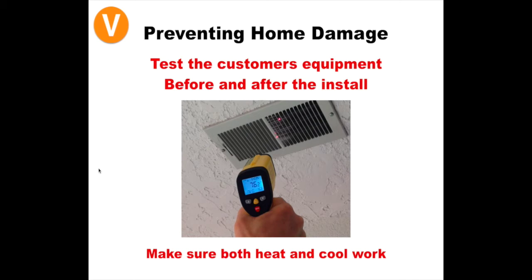You're taking temperature readings with your thermometer to make sure everything's working on the heat and the cooling side before you ever do the install. If it's not working, we want to make sure that we talk to the customer, let them know that the system isn't working, and we're more than happy to come back out and do the install when the system is working. You can still finish everything else on the install, but when it comes to the thermostat, we don't want to install the thermostat until everything's working 100%. So definitely use those infrared thermometers that you're going to receive in your toolkits. Make sure you're confirming that it is warm air blowing through the vents in heat mode, and it is cool air blowing in the vents for cool mode, and just save yourself a lot of headaches on that. So testing is very important.